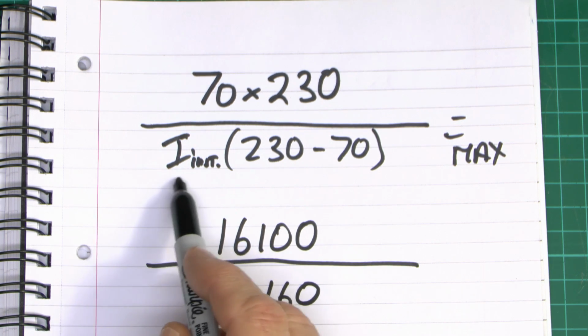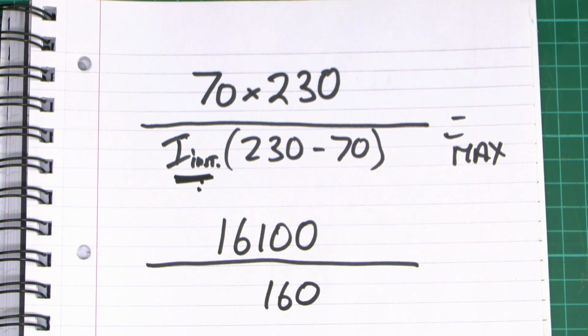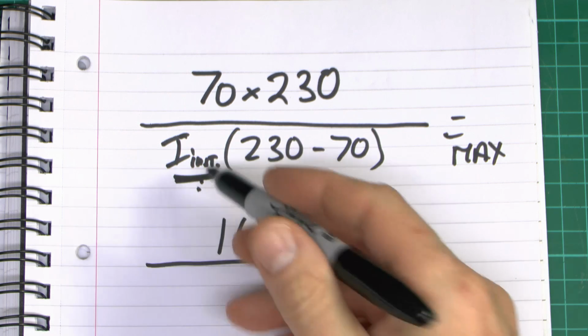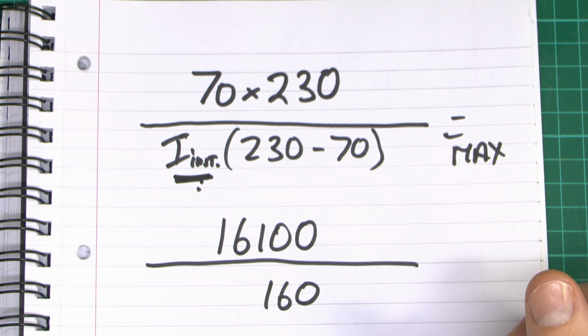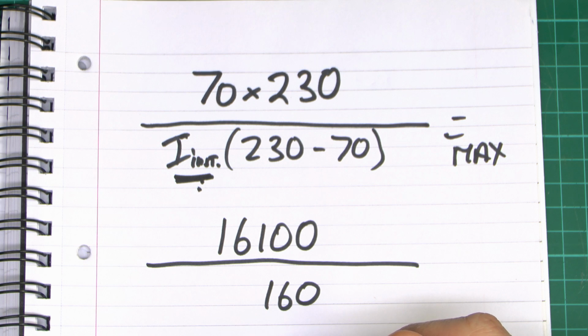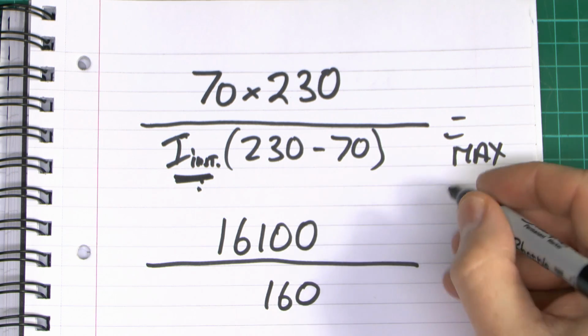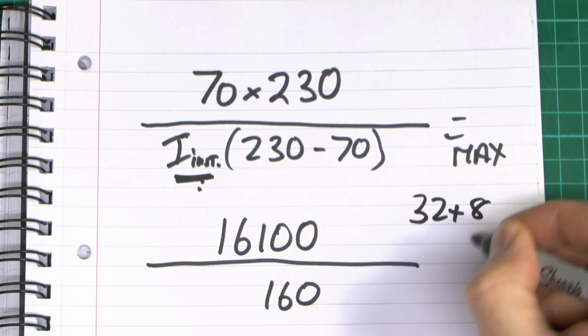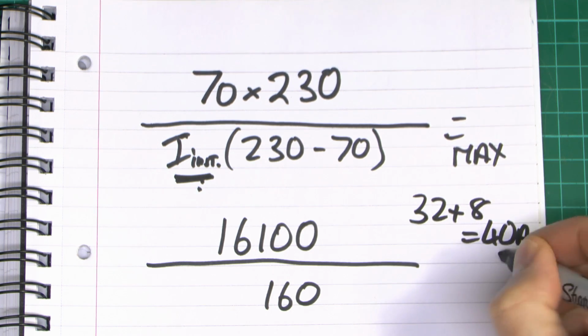And then the I inst, which is the load of the installation. And we can put in a sensible value here. Now, bearing in mind, this has to include the load of the particular charging vehicle. So that's going to be in the region of 32 amps or so. And then we have to add on, of course, any other loads within the property itself. So, of course, that's generally whatever happened to be in there. So let's go for a fairly low value to start with. So let's say we had the 32 amps for the actual thing there, and let's have a really implausible, say, 8 amps for the installation itself. So, of course, that will be 32 plus 8. That will give us a total load of around 40 amps there.